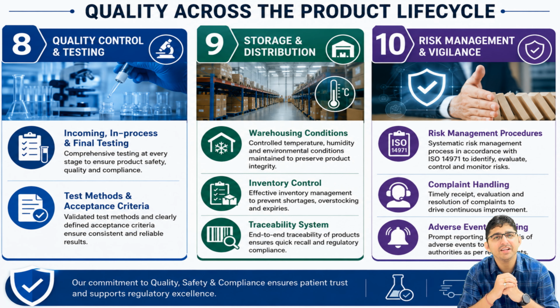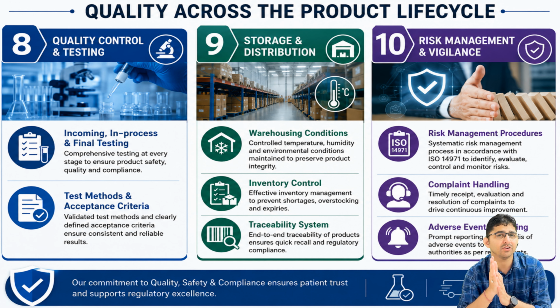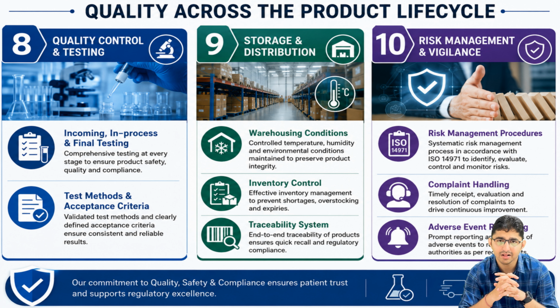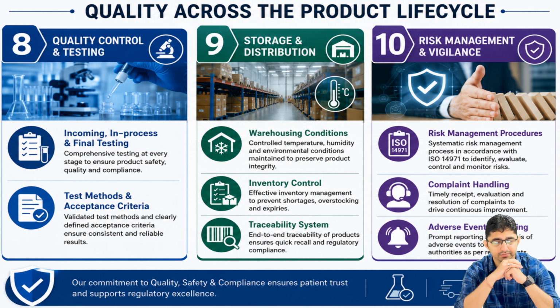Then there is a very important topic, which is the risk management and the vigilance. So the risk management procedure as per ISO 14971 should be incorporated in your PMF, or a reference should be given for a risk management SOP, the complaint handling and the adverse event reporting for the medical devices when it fails in the field.